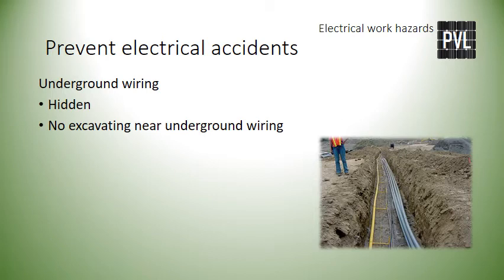Underground wiring is generally hidden from view and can be buried only inches from the surface. There is a danger of damaging underground wiring when excavating and causing harm to persons. Before excavating, even by hand, a permit must be granted to prevent contacting a live underground wire. If working in the electrical system of an existing structure, the service entrance drop is often an underground wire or cable called a feeder that follows a direct path from the transformer to the service entrance panel. When a permit is acquired, the area to avoid excavating will be clearly marked by the power provider.